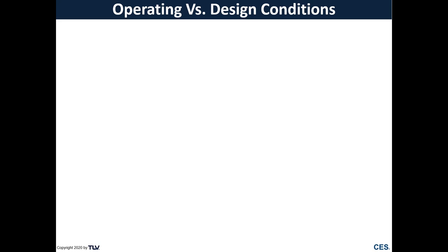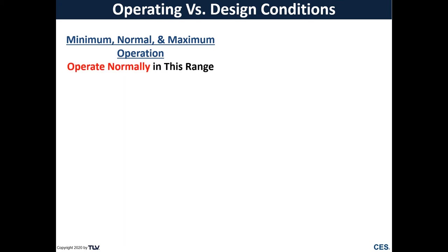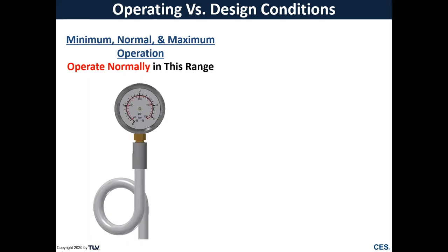Now, looking at operating versus design conditions. Our operating conditions, we have our minimum, normal, and maximum operating conditions. This is referring to our temperature and pressure. And this is the conditions at which our steam trap needs to operate normally at within that range. So if we look at pressure, for instance, we may be operating at a normal pressure, but that application may have a range of a minimum and a maximum that that trap must meet.